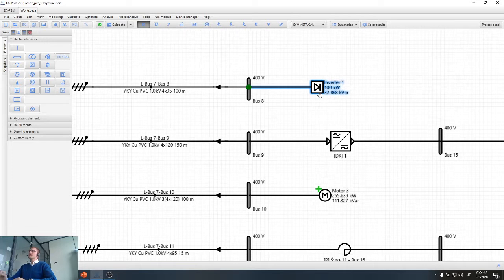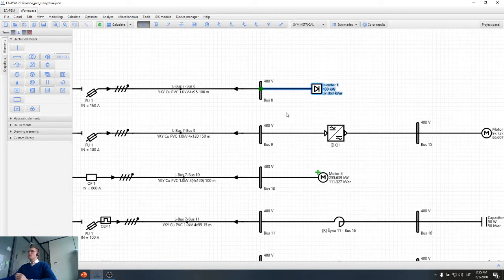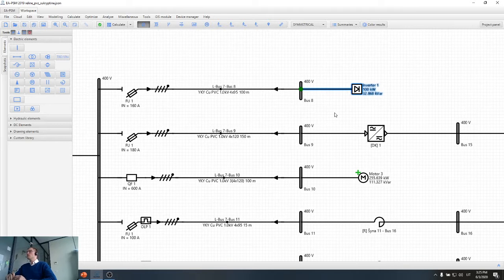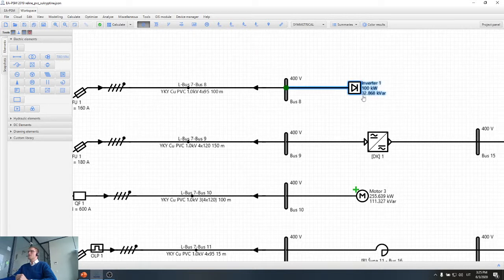The inverter, as a device, is very sensitive to imbalanced voltage and also to low voltage. Because it is so sensitive to these kinds of conditions in the electrical network, most inverters already have under voltage protection devices incorporated inside. When we have low voltage conditions, currents inside the inverter and inside its thyristors increase, and because of that the inverter starts to overheat. To avoid this scenario, inverters already have under voltage protection incorporated.